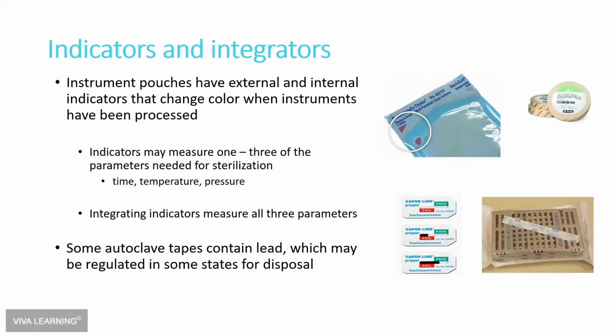And there are some that are class 4 or type 4, as they're called now. Some are class 5, although there aren't any class 5s that I know that are in pouches. The class 5s are typically the integrating indicator strips that you put in. And they give you, here's another example on the left-hand side, they give you this indication that the cycle has failed or it's passed. So again, the integrating indicator should be 1 per load according to CDC. But if you're using a wrapped cassette or a pouch that doesn't have internal indicators, then you need to use an indicator strip.